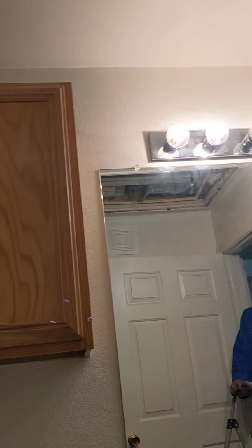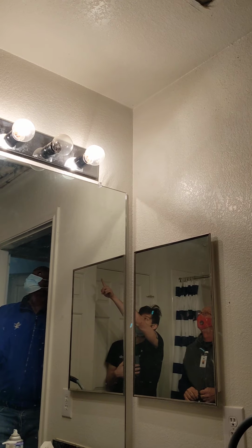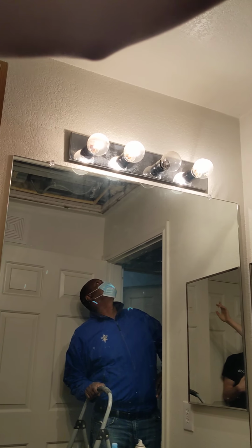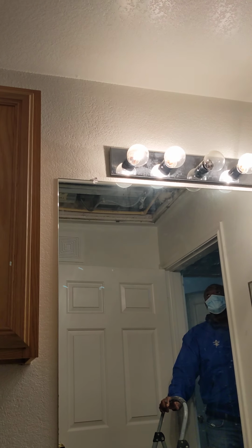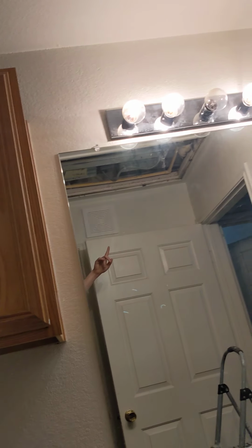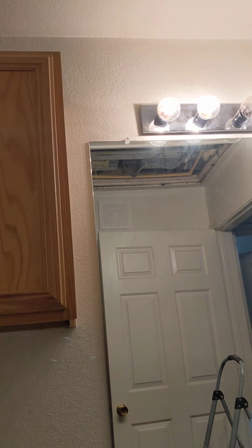The blower? Yep. Okay. And then that's where you get that wood, and then that towel, which is just dark with rust. I'm not denying that is most likely rust. Yeah, this up here. Yeah, definitely. That's all just rust from the condensation line, and from this, and from the pan overflowing constantly. Exactly. That pan was overflowed constantly. My concern is that shaft runs all the way over there. Right.